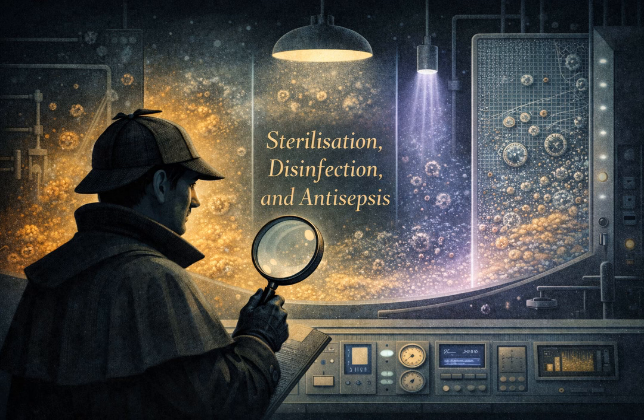But the magic trick is what happens when you turn the machine off. The plasma collapses back down into harmless water vapor and oxygen. So there's no toxic residue to worry about. None whatsoever. There's no need for a long aeration time. You can use the instrument almost immediately. It's far safer for the staff and for the patient. It has largely replaced ETO for many applications. Its main weakness, though, is that it struggles with really long, narrow lumens, like long tubes, where the plasma can't fully penetrate deep inside.